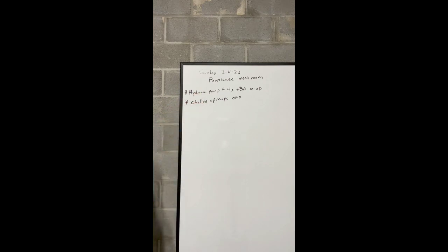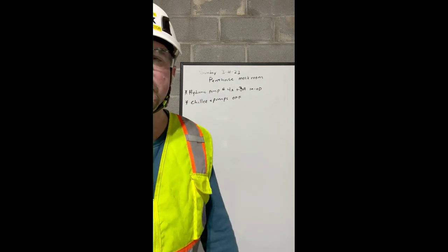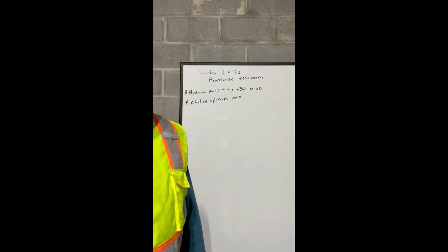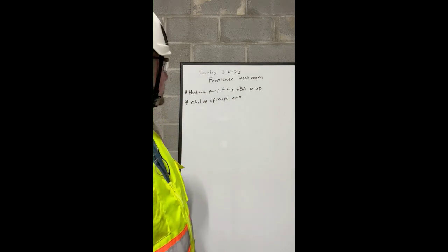So for instance, I have hydronic pump number 4A and 3A inoperative. That's because there are some seal and gasket leaks. We have those shut off. Chillers and pumps that support the cold water chilling system are also turned off because it's very cold outside, so we're not going to need those for a little bit. The outside air temperature, also called OAT, you see those acronyms and different things for HVAC, is right around 29 degrees today. Usually we'll turn those chiller systems on right around 40 to 50 degrees outside air temperature. So with that being said, let's start our tour.